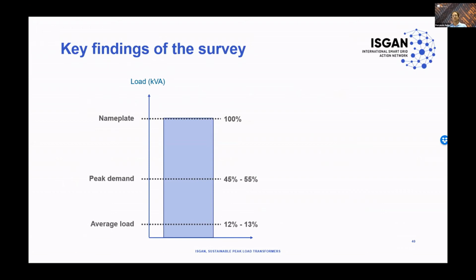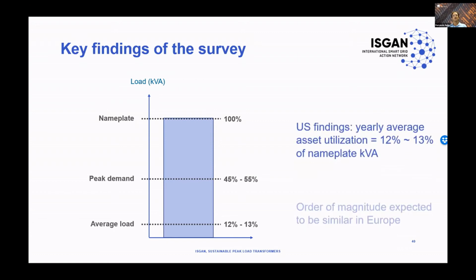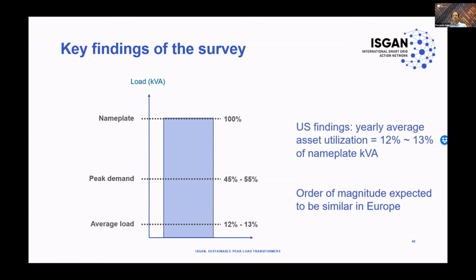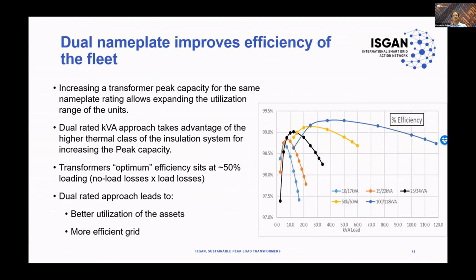So this means that we are well on the left side of the curve that we mentioned before. We can expect a similar order of magnitude of loading in Europe. As Alan commented before, for several transformer designs of several nameplate capacities, 17, 22, etc., up to 118, the best efficiency occurs at roughly 50% of the load.